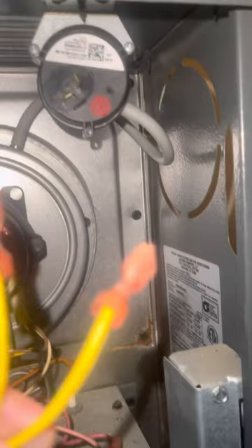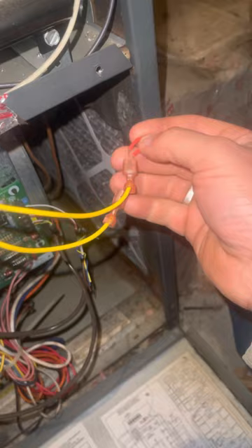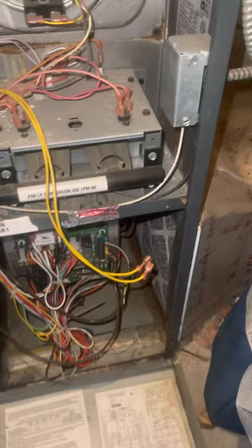I unplugged the two wires that were there and what I did was I used this pin to jump the two wires together, and the furnace kicked on once I turned the power back on. You want to have the power off whenever you deal with anything here.